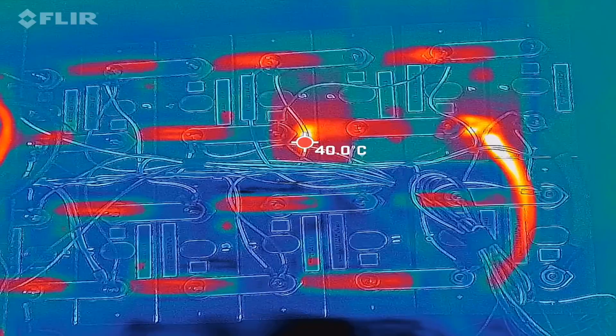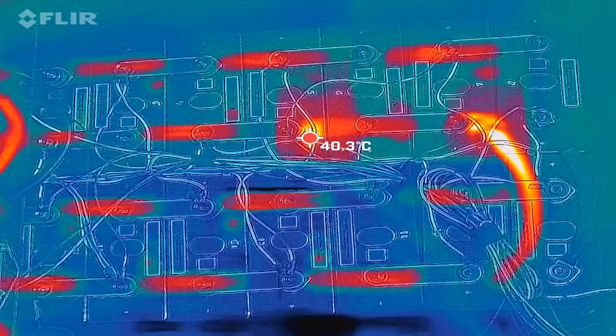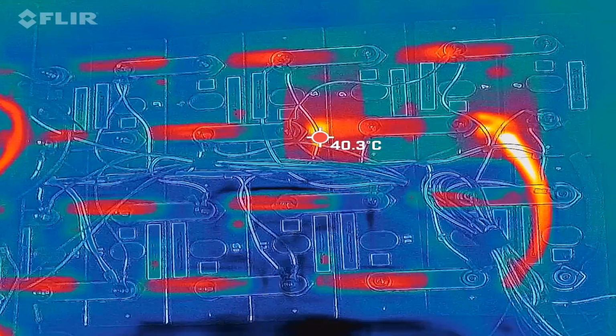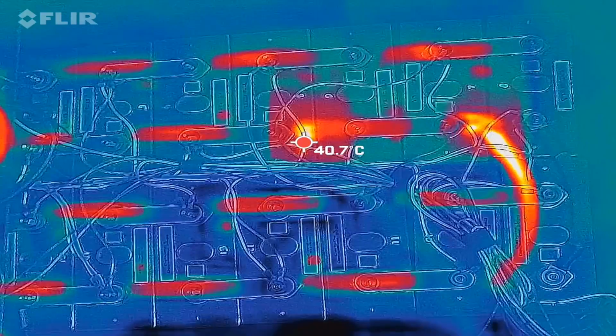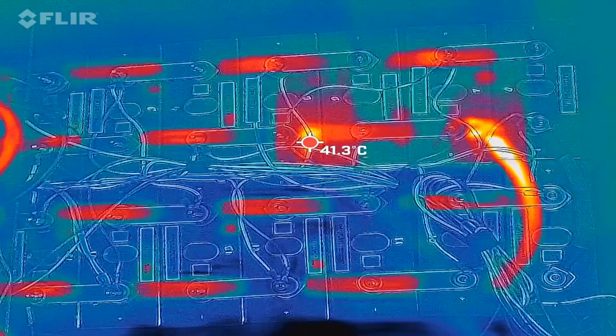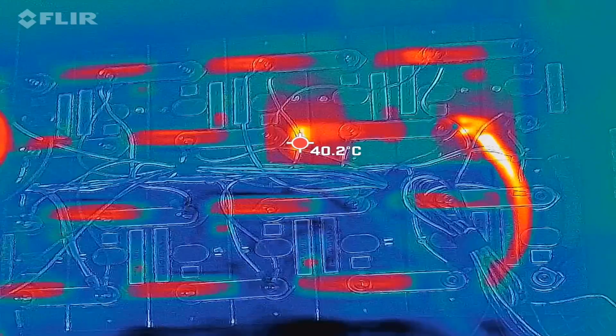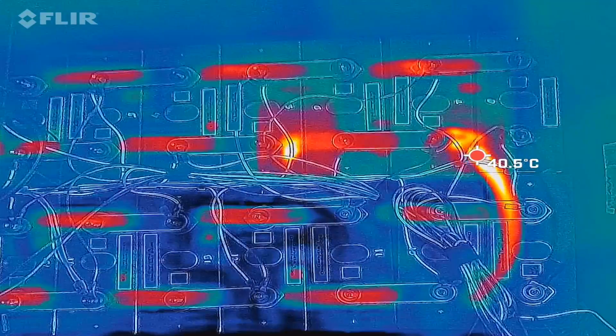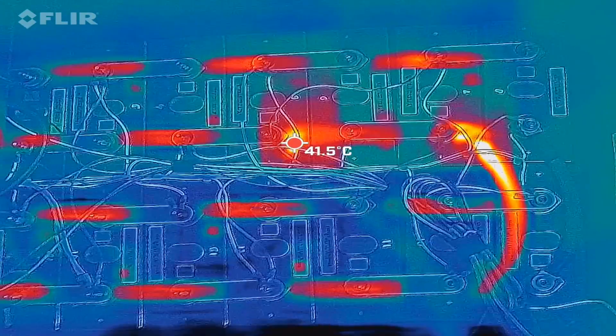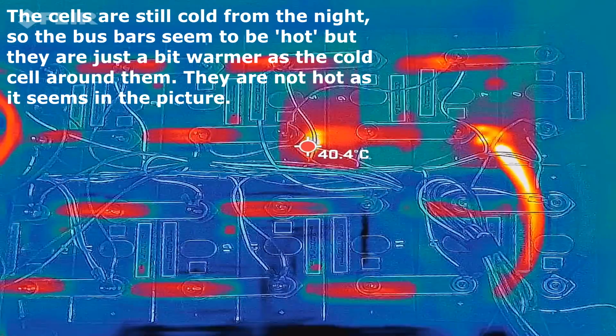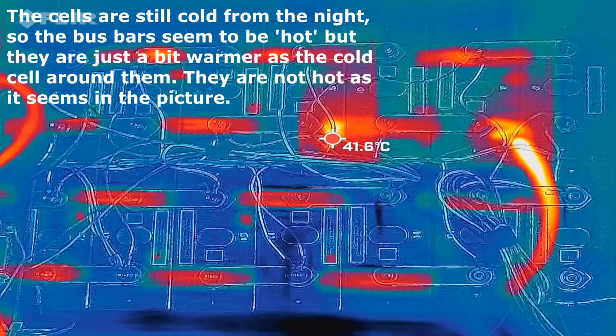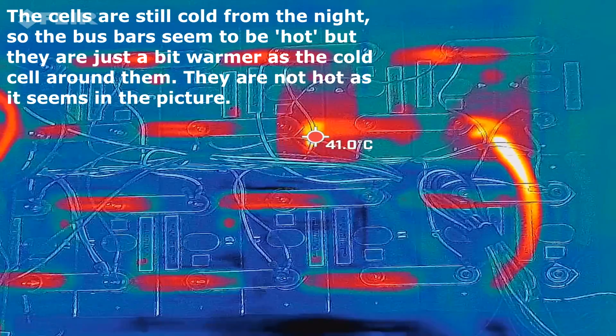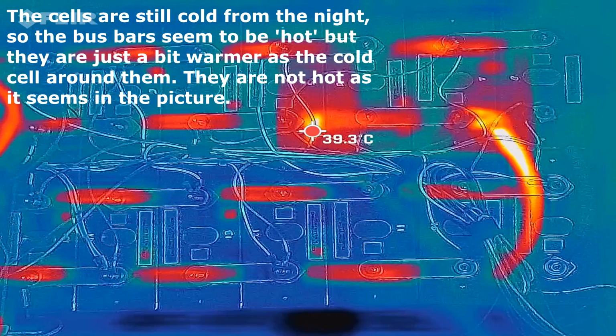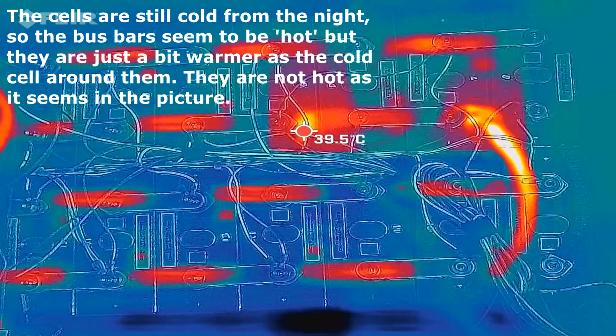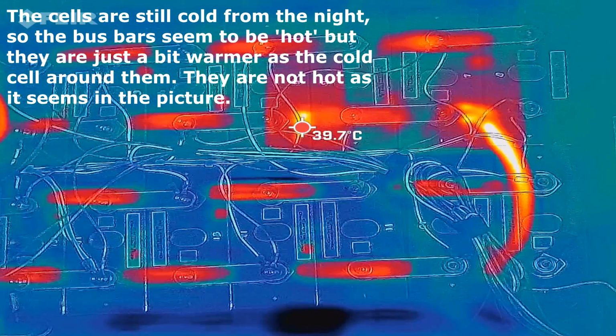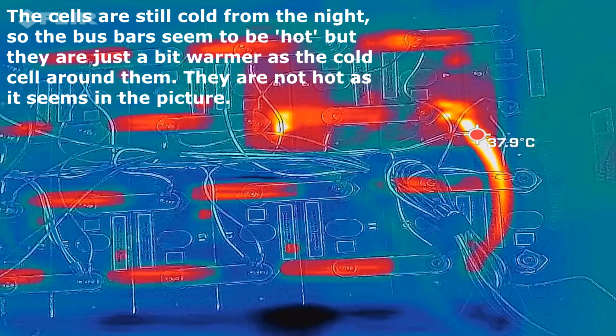This was one of my first crimps, and obviously it wasn't the best one. You can see how the heat actually spreads into the cells—it's not just the connection where the bus bar hits the terminal, it's the whole surface of the battery cell that's heating up. You can see all the other bus bars getting warm a little bit, but not by much. Cell number 6 is definitely at 39, 40 degrees now, terminal temperature—this is our faulty terminal.